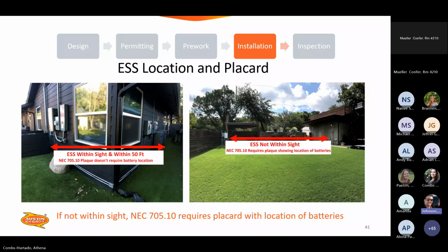All right, ESS and panel location. So let's see. The plaque that we need, if everything is not in the same location, has to denote where the service is and where the ESS location is. So if there's ESS on one side of the house completely, or even around the corner, for the first responders' sake, we need to have it to where they can see, okay, there's the rapid shutdown sticker, there's the ESS placard, all right, there's other sources of energy on this site. If they're trying to turn electricity off because of an electrical fire and there's 4 different sources of electricity, they need to know that because they're going to turn one off. Okay, cool. It's still burning. They're going to turn another off. It's still burning. It won't shut off. That's what the placard helps them with, is finding all the locations where all the shutoffs are at.